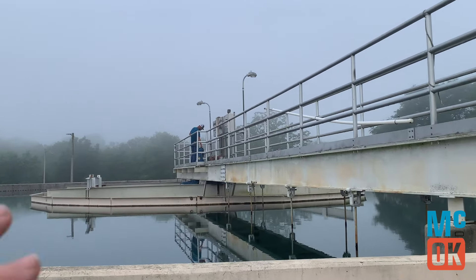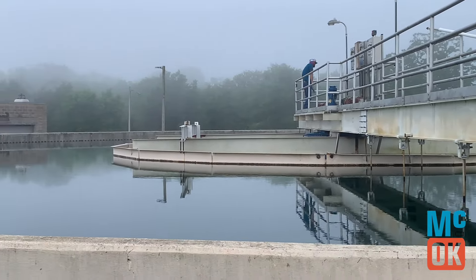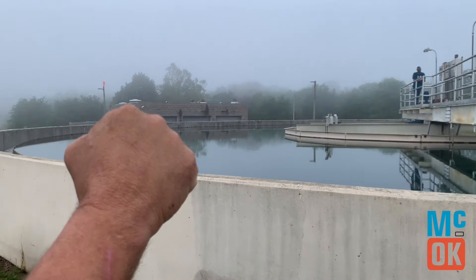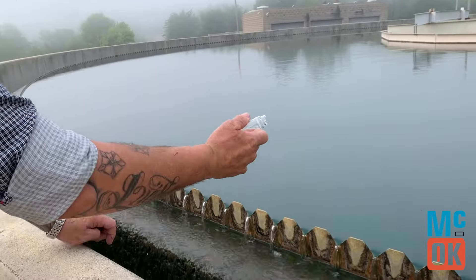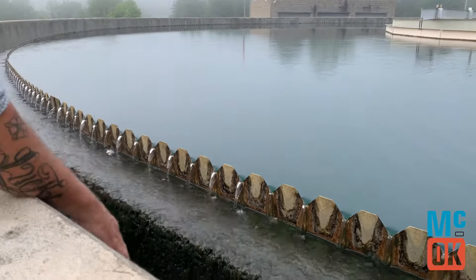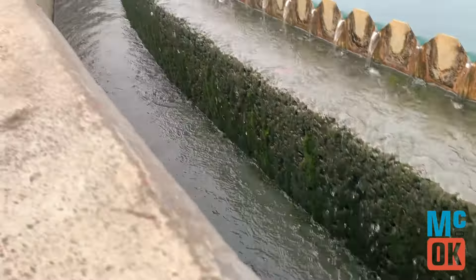It makes a blanket, the water comes up through that blanket, and as it comes through — that's why they call it upflow clarification — the blanket binds up even more dirt and creates more blankets. This is our weir system. Whenever the water comes up, it flows over these weirs, goes into this trough, and flows out, and then goes to the filter building.